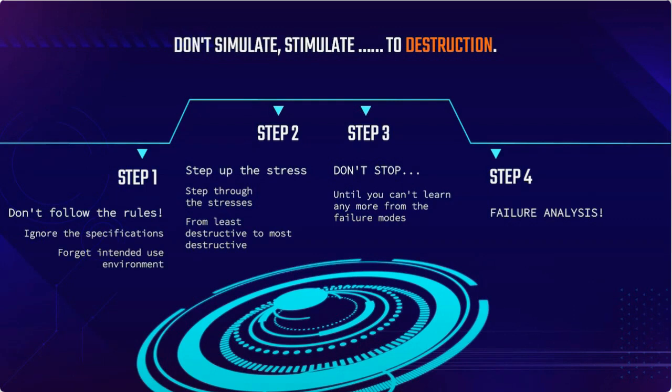So you keep going until you've got all the failure modes you can get your hands on, and then comes step 4, really the most critical step in HALT, the failure analysis. It is very important to understand all the failure modes that happen in HALT.